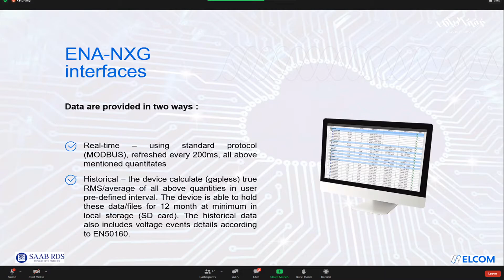Speaking about the data from the meter, we can provide it in multiple ways. Usually for real-time values, we provide it using Modbus or the 104 protocol. For historical values, we try to be as open as possible, storing data into CSV files locally on the SD card. The SD card can be accessed by FTP, SFTP, web services, or some cybersecurity protocols if needed. So we try to be most open with this meter so it can be integrated into any third-party central system.